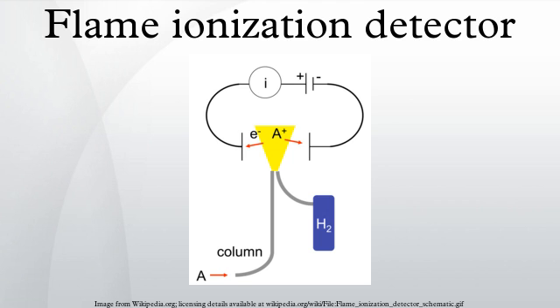Operating principle. The operation of the FID is based on the detection of ions formed during combustion of organic compounds in a hydrogen flame. The generation of these ions is proportional to the concentration of organic species in the sample gas stream.